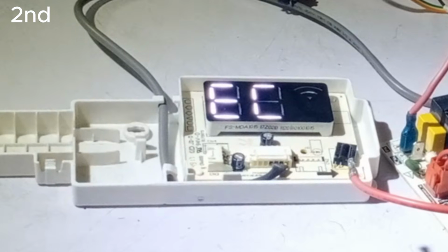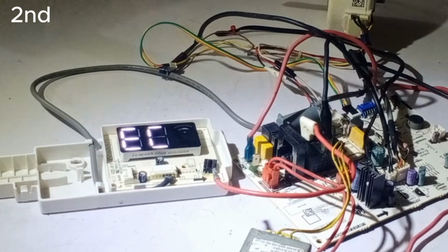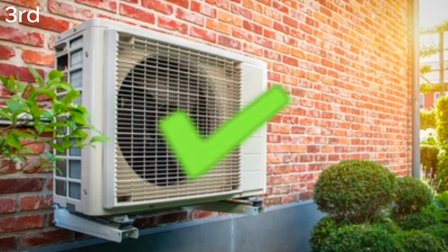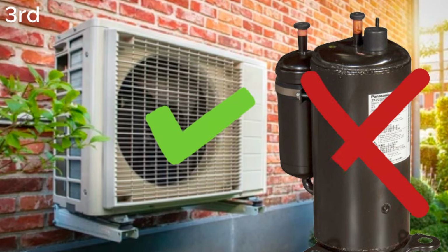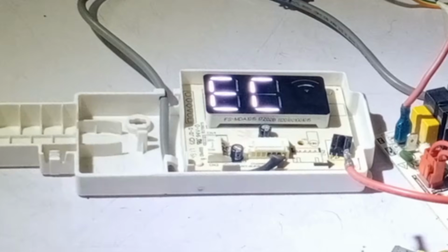The second reason could be if the compressor's wire is burned. Still, the unit will show you the EC error code because the compressor is not working. The third reason could be that if everything in the unit is fine, the compressor itself is bad. The unit will still show the EC error code.